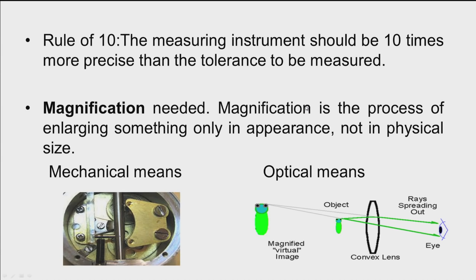There is another important term: the rule of 10. The measuring instrument should be 10 times more precise than the tolerance to be measured. If the tolerance levels of the component are in terms of 0.1 or 0.2 millimeters, then we need to select an instrument capable of giving readings of 0.01 or 0.02 millimeters.